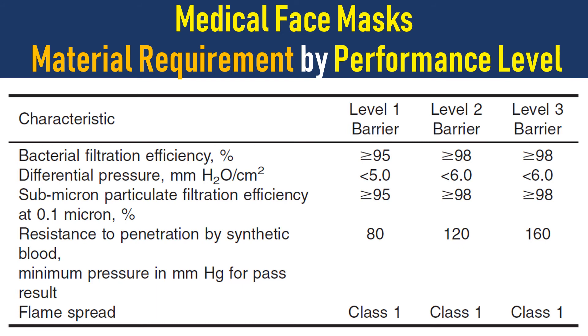Differential pressure, which represents breathing resistance, should be less than five for level one barrier. For level two it should be less than six, and for level three it should also be less than six.